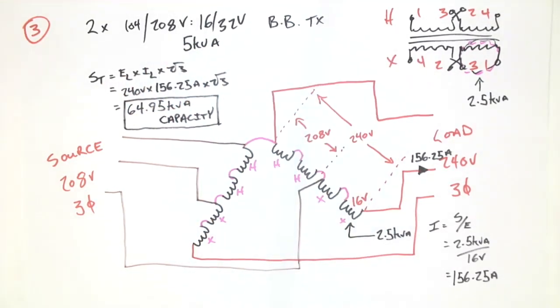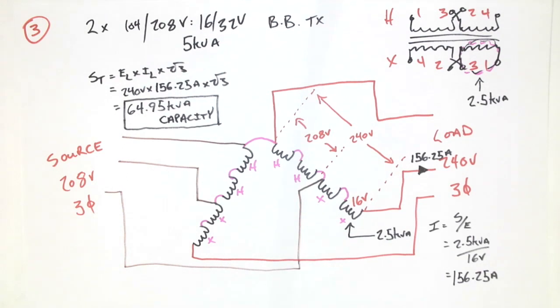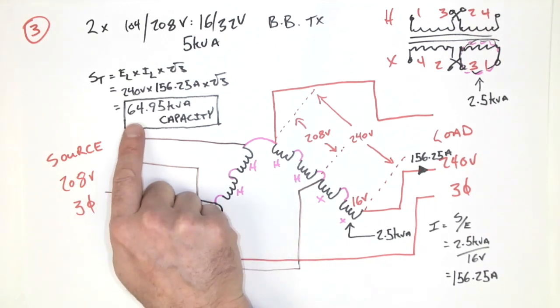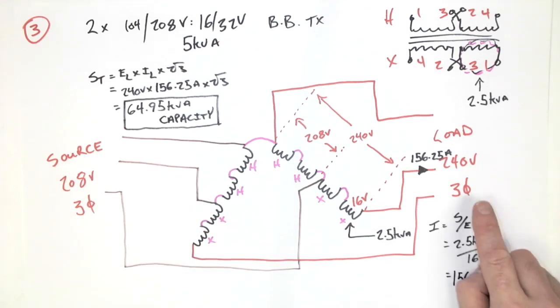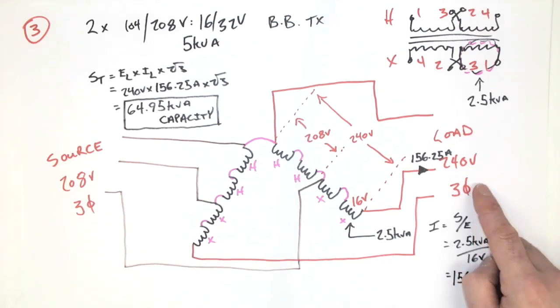So take a look. What did we use for the connection? We used two 5 kVA rated isolation type transformers. Because we connected them in auto, and because we chose to do an auto open delta connection, the increases in efficiency are monstrous. We can supply almost 65 kVA worth of 240 volt three-phase load. It's monstrous. So just be aware, massive increases in capacity are actually quite common. This is a 13-time capacity increase from 5 kVA. Well, I guess we have two of them, so 6 times.